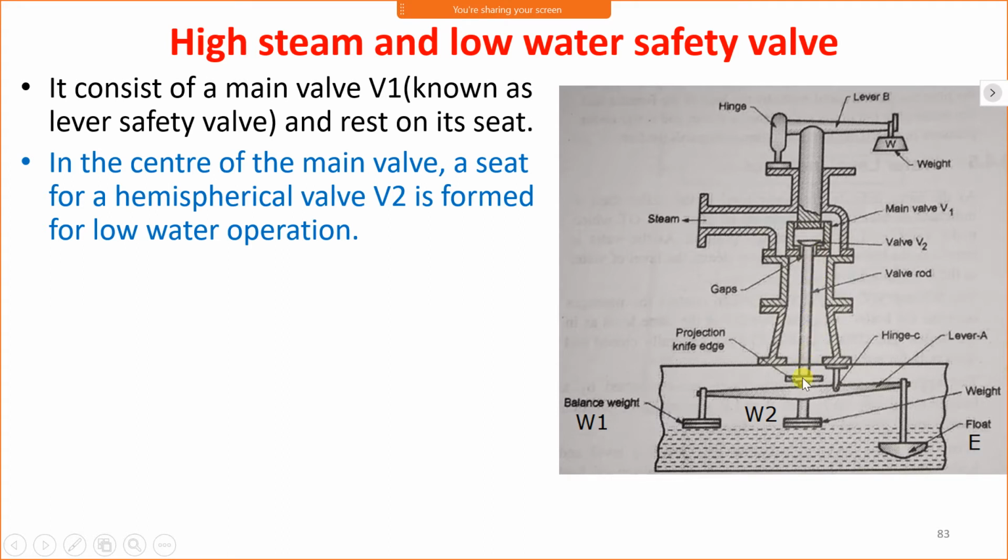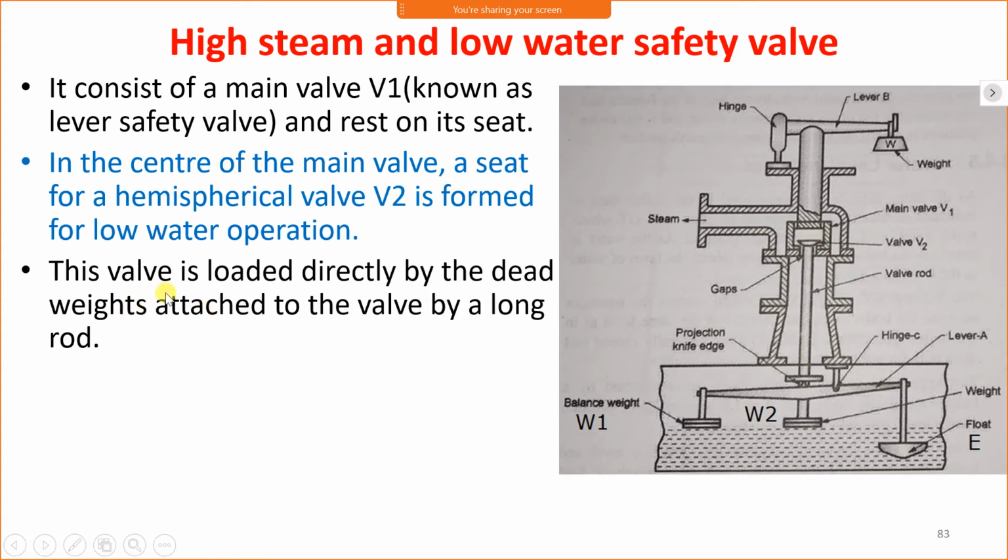When the water level is low, this valve will operate. This valve is loaded directly by the dead weight attached to the valve by a long rod. Look at here, at the end of this rod there is a weight W2. This weight W2 pushes this valve V2 on the seat.